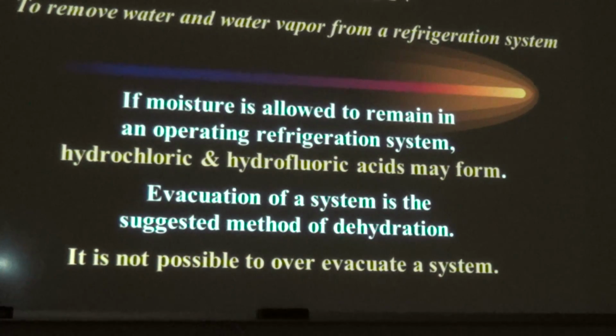Dehydration is what we refer to when we use a vacuum pump. It is to remove water and water vapor from a refrigeration system. If moisture stays in the system, let's say it's an R22 split air conditioner, they were called wet systems. They liked water. If you have water vapor that stays in the compressor, they'll form hydrochloric and hydrofluoric acids. And the way to get rid of this is to use a vacuum pump, evacuate the system, and then we will be able to remove the moisture. One thing to keep in mind that they want to emphasize is that you can never overdo it with the vacuum pump. You can't damage a system by keeping it in a low vacuum for a long period of time.